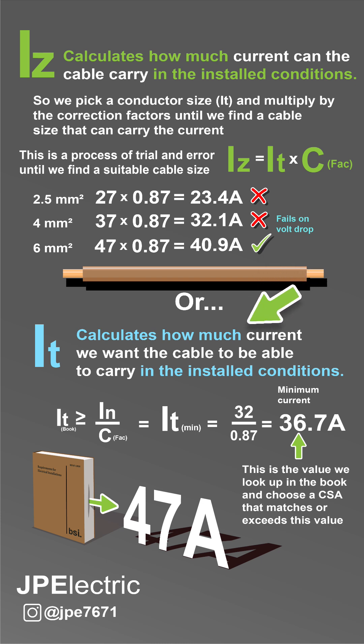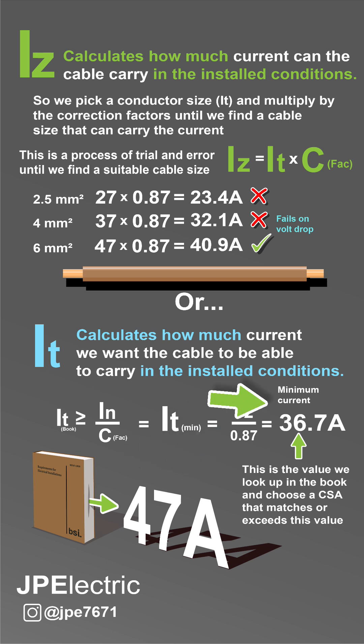So you have the method to find IT. We calculate how much current we want the cable to carry. IT is the book value. This formula — IT greater than IN divided by correction factors — will give you IT minimum. This is the minimum current that we need the cable to be able to carry. We look through the book, going up to 6mm cable which can carry 47 amps.